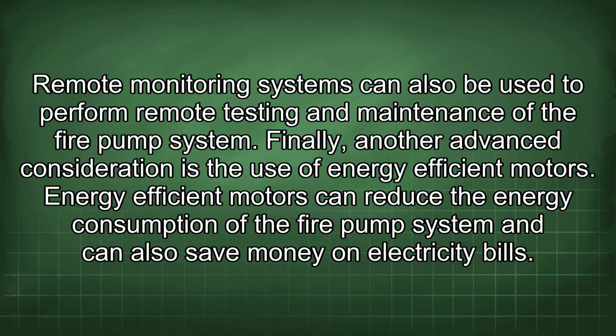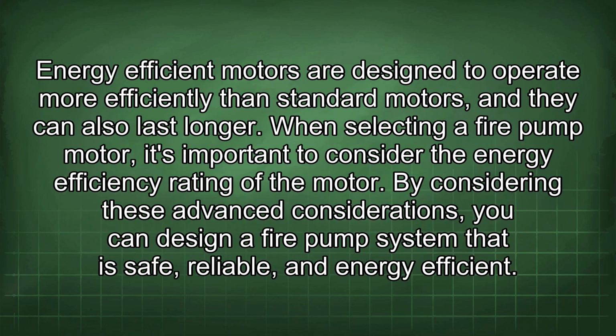Finally, another advanced consideration is the use of energy-efficient motors. Energy-efficient motors can reduce the energy consumption of the fire pump system and can also save money on electricity bills. Energy-efficient motors are designed to operate more efficiently than standard motors, and they can also last longer. When selecting a fire pump motor, it's important to consider the energy efficiency rating of the motor.